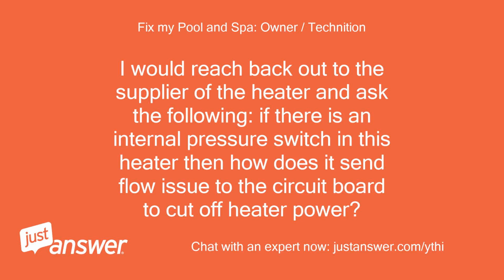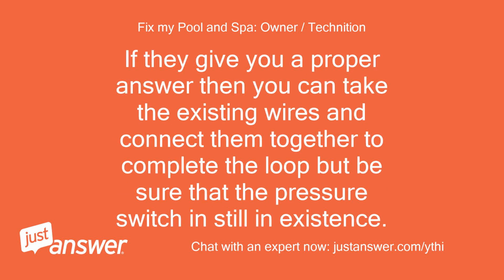I would reach back out to the supplier of the heater and ask the following: if there is an internal pressure switch in this heater, then how does it send a flow issue to the circuit board to cut off heater power? If they give you a proper answer, then you can take the existing wires and connect them together to complete the loop, but be sure that the pressure switch is still in existence.